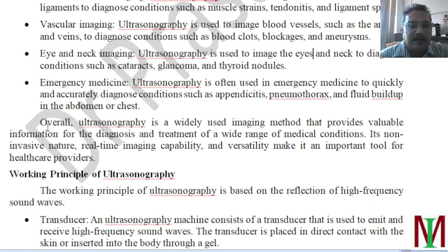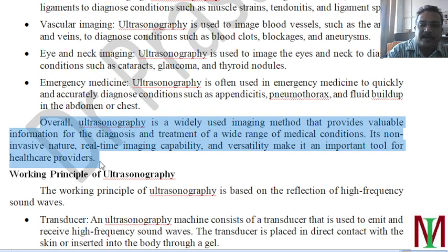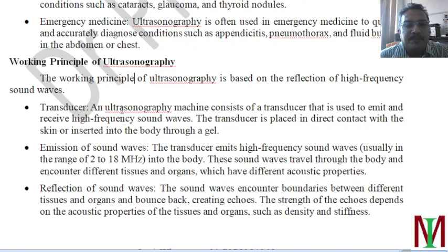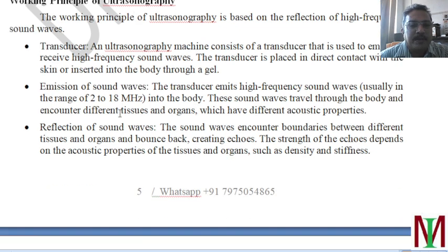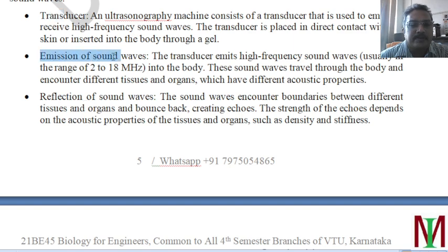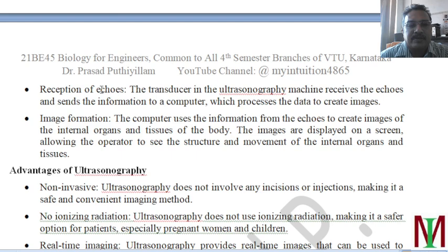So overall, I don't want to delete it. Okay, working principle of ultrasonography. It is based on reflection of high frequency sound waves. It has a transducer which emits sound from 2 to 18 MHz. Reflection of sound waves takes place, the echoes are received and converted into an image.